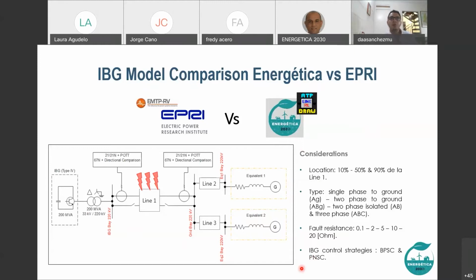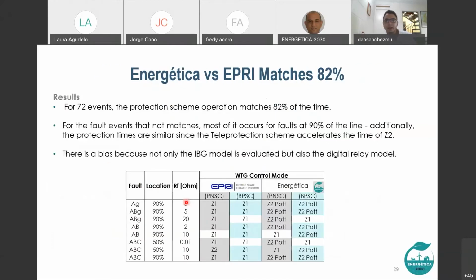Okay, in this case, we compared the operation of the protection scheme placed at each bay of line 1. Check out this. Here we have a protection scheme: distance protection with POTT teleprotection, and ground overcurrent with directional comparison at each side of line 1. And the result of this exercise has a good percentage of coincidences. EPRI and Energetica match in 82% of the fault cases. And in the cases that we don't match, the fault location mostly was 90% of the line. Here we can see how EPRI usually operates in zone 1 for location 90%, but Energetica operates in zone 2 with time acceleration given by POTT teleprotection. So at the end, the results were satisfactory.